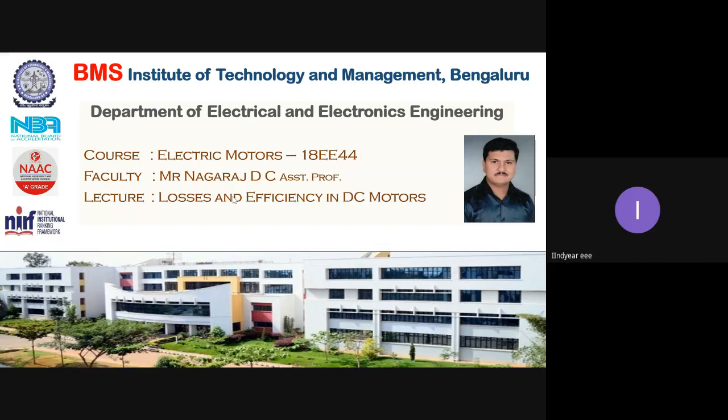That minimum power utilized to overcome the resistance is copper loss. Similarly, in the iron parts, to overcome the hysteresis effect and eddy currents, some amount of power is utilized by the iron part, which we call iron loss. Because of mechanical friction in the physical moving parts, some amount of input power is utilized to overcome that friction, and beyond that friction the output has to be given out. That amount of power utilized to overcome friction is called mechanical loss.